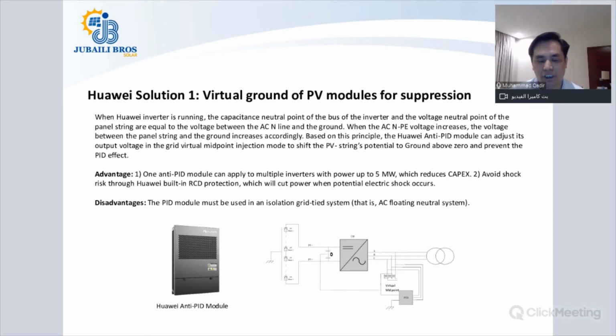Now, this positive potential that has been created by the Anti-PID module is used internally inside the inverter to cure the PID effect on the DC string side. Now, the benefit with using the Huawei Anti-PID module is that you will be using one Anti-PID module for up to 5 megawatt of PV plant. This will reduce the capex and the initial expense of your PV plant, and since Huawei inverters also have the RCD, any shocks will also be avoided due to the RCD protection.